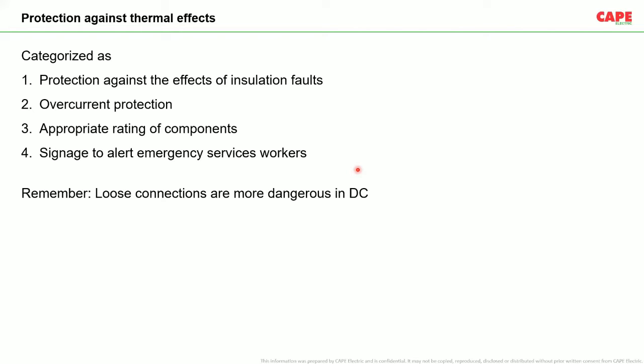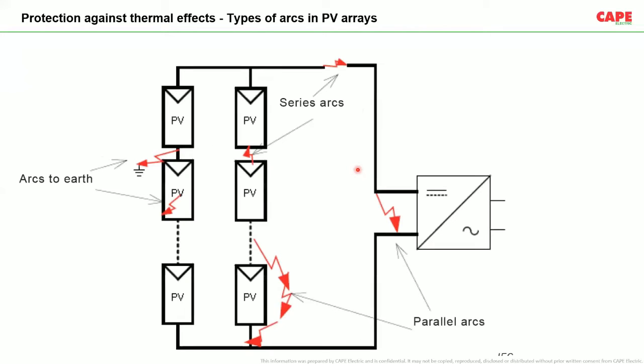Now we go to the complicated part of the presentation. Today we are going to discuss only protection against the effect of insulation fault, that is, how to eliminate an insulation fault in a solar PV, especially on the DC side. First, you should understand the types of insulation failure and the types of arc in a PV system. In the picture, you can see there are three types of arc.